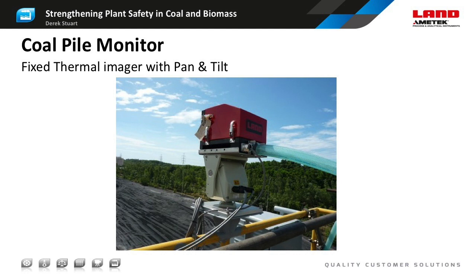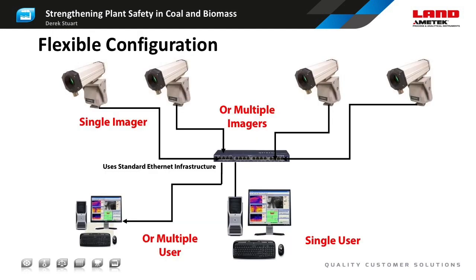Infrared thermometry is a non-contact technique that allows for remote temperature measurement. An infrared imager can give a two-dimensional map of the surface temperature of the stored fuel. It's important to note that infrared temperature measurements can only determine the surface temperature, so they may miss a buried hotspot. However, the heat generated by the oxidizing fuel will eventually warm the surrounding material, and the hot carbon monoxide given off will transfer heat to the surface through convection. A study by Fierro and colleagues noted that infrared thermography is very efficient at detecting hotspots in coal piles, and losses calculated using the technique correlate very well with those measured directly using thermocouple probes. Depending on the size and geometry of the storage area, several separate thermal imagers may be needed to cover the whole area. The system illustrated here has four imagers with two remote consoles displaying, processing, and storing the data.